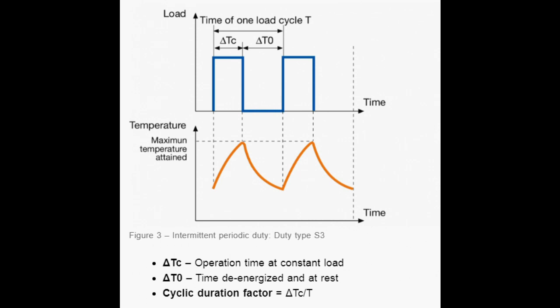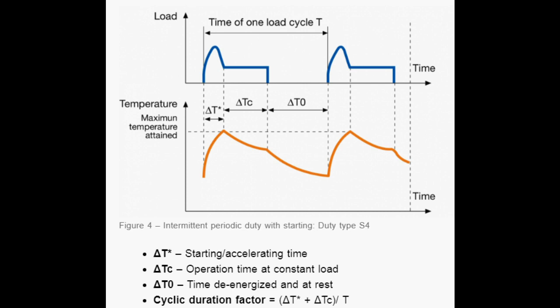From type S3 to type S8, these are periodic duties. In S3 type, we have a sequence of identical duty cycles, each including a time of operation at constant load and a time de-energized and at rest. In S3, the starting current does not significantly influence the temperature rise. In S4 type, we have a sequence of identical duty cycles, each cycle includes significant starting time, a time of operation at constant load, and a time de-energized and at rest.